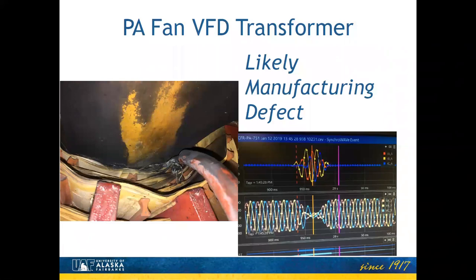Normally, there's just a normal wave pattern that you see on both sides of that event, and what happened at that point, there was initially a phase to ground short detected, and then that created a big plasma cloud inside the generator cabinet that initiated a phase to phase short and took out the rest of the transformer. Mm-hmm. And all that is an event that happens within milliseconds. Yep. But we do have a replacement VFD powering the fan right now. And the manufacturer is sending us a replacement transformer to put in its place so we can put the original one back in service.